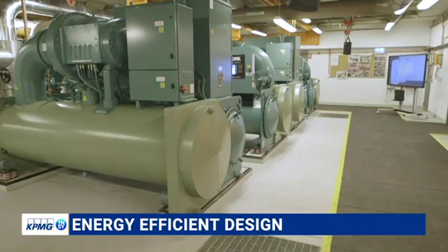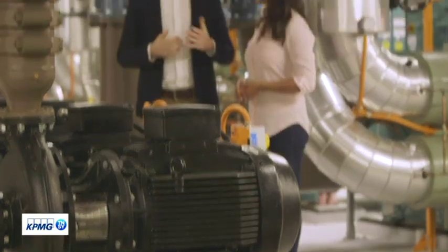We're actually sucking up seawater. We're rejecting the heat that we take out of all the theatres, the concert hall, the opera theatre, and we're putting that into the seawater. We're constantly pumping cold water around the building, so we're pumping 6-degree cold water constantly around the building, which is how we reject all of the heat into the water.